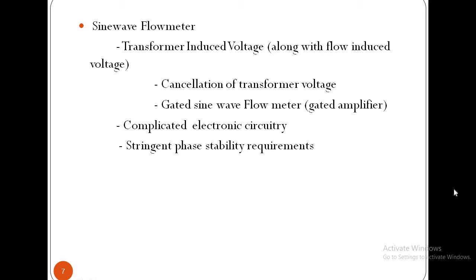As a result, in addition to the induced flow voltage, there is an induced artifact voltage, generally referred to as transformer voltage. The transformer voltage is much larger than the signal or flow induced voltage and is 90 degrees out of phase with it. This also causes baseline drift, which necessitates high phase stability in the amplifier and the demodulator circuits.